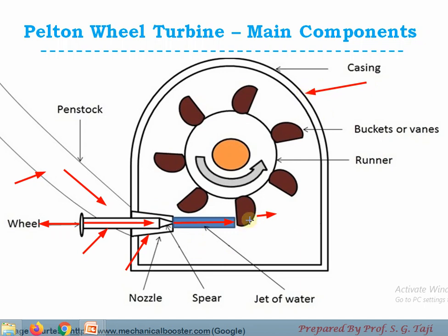The next component is the casing. Whenever the jet of water strikes on the blade, some splashes of water come out due to the striking, and those splashes will be prevented by the casing and safely discharged to the tail race. The casing does not serve any hydraulic function in the case of Pelton wheel turbine because the Pelton wheel turbine works totally under kinetic energy, and whatever pressure is available at inlet and outlet of the Pelton wheel turbine is atmospheric pressure.